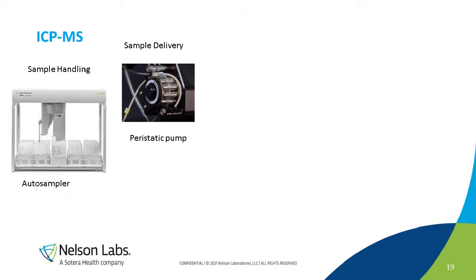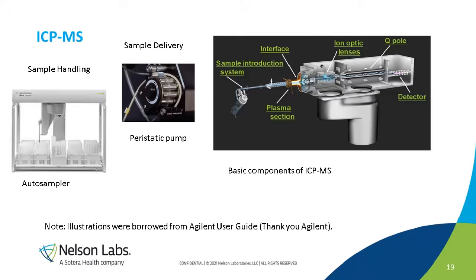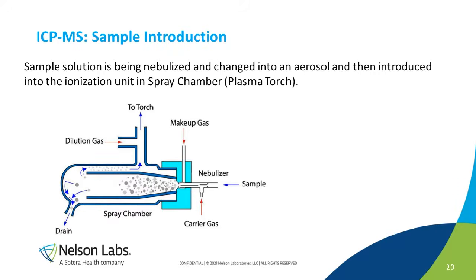Next is actually the showing about the instrument. Obviously there should be the sample handling step required. We use an auto sampler, and then there should be a sample delivery. The peristaltic pump is available, and then delivery into the mass spec here.